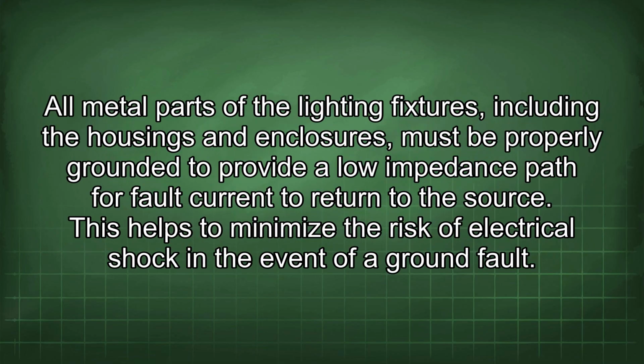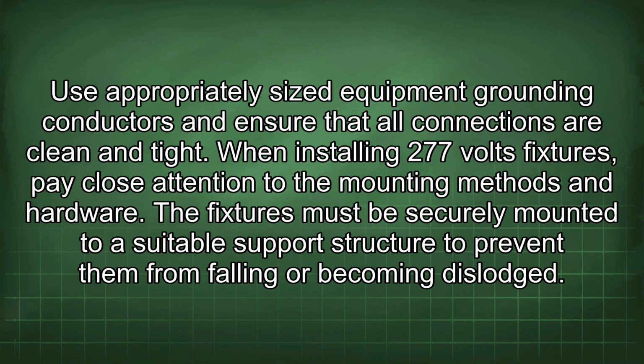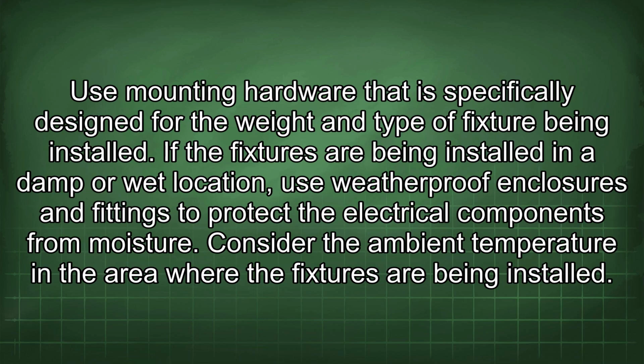All metal parts of the lighting fixtures, including the housings and enclosures, must be properly grounded to provide a low impedance path for fault current to return to the source. This helps to minimize the risk of electrical shock in the event of a ground fault. Use appropriately sized equipment grounding conductors and ensure that all connections are clean and tight. When installing 277 volts fixtures, pay close attention to the mounting methods and hardware. The fixtures must be securely mounted to a suitable support structure to prevent them from falling or becoming dislodged. Use mounting hardware that is specifically designed for the weight and type of fixture being installed.